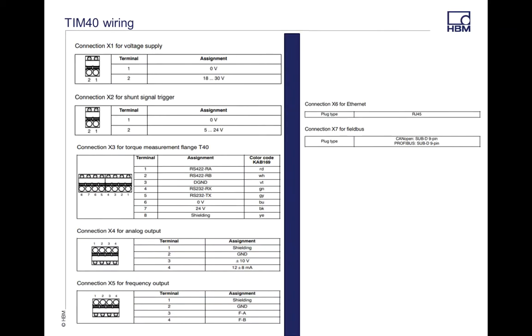Here's another example of the wiring and all the details. This is found right in our manual — you can go right through that in the TIM40 manual. Again, X1 is 18 to 30 volt supply. X2 is your shunt value, 5 to 24 volts. This is the color coding for your cable, your digital cable.